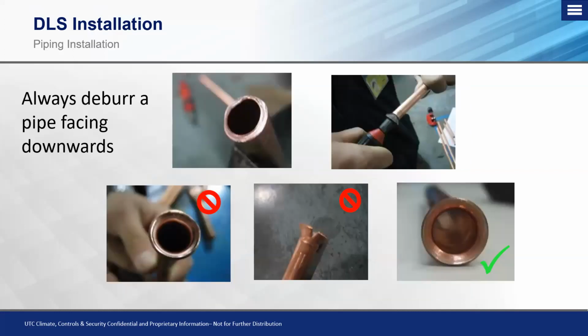After you cut your pipe, you need to make sure that you're deburring your pipe. Because we are making a mechanical press fitting, we need to make sure that when we deburr, we have our pipe facing downwards. We take our deburring tool and slowly work that pipe to clean up those edges, and then just give a soft blow through the pipe or get a rag and clean up those little metal shavings, because if they sit on the pipe when you go to press down and make your flare fitting, they can cause nicks in the surface of the flare, which can lead to refrigerant leaks over time. So again, it's all in the preparation. We need to make sure that we're cutting correctly. We need to make sure that we're deburring facing downwards and getting those metal shavings out of there.